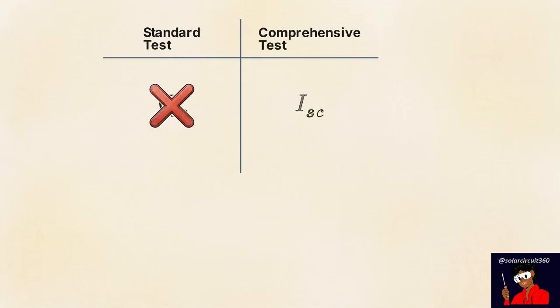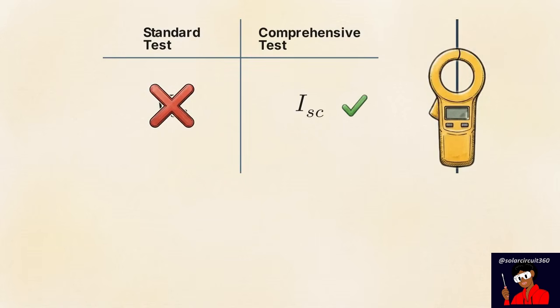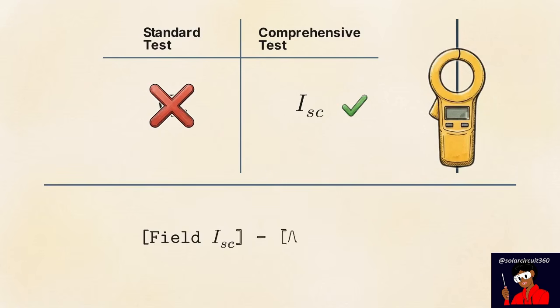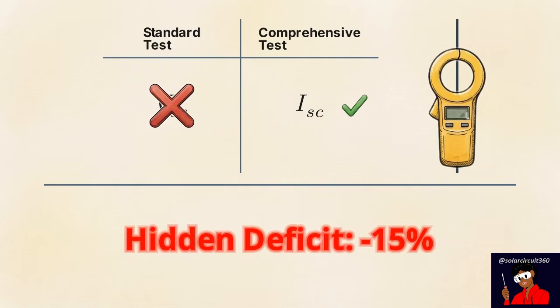Stop relying on open-circuit voltage tests. Technicians must measure the short-circuit current of individual strings using a calibrated DC clamp meter. Those field readings must be carefully compared to original spec sheet ratings, adjusted for current sunlight conditions. This calculation isolates the exact current loss to degradation.